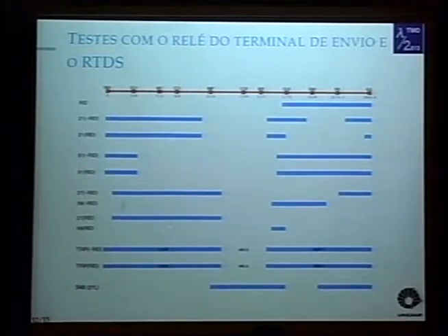So as we have shown, when we have a fault in the middle of the line, the forward substations after Colina 2 are in an under voltage state. And since the substation of Serra da Mesa 2 is physically close to the substation of Serra da Mesa 1, we saw the possibility of analyzing the behavior of an under voltage relay located on the substation of Serra da Mesa 2.